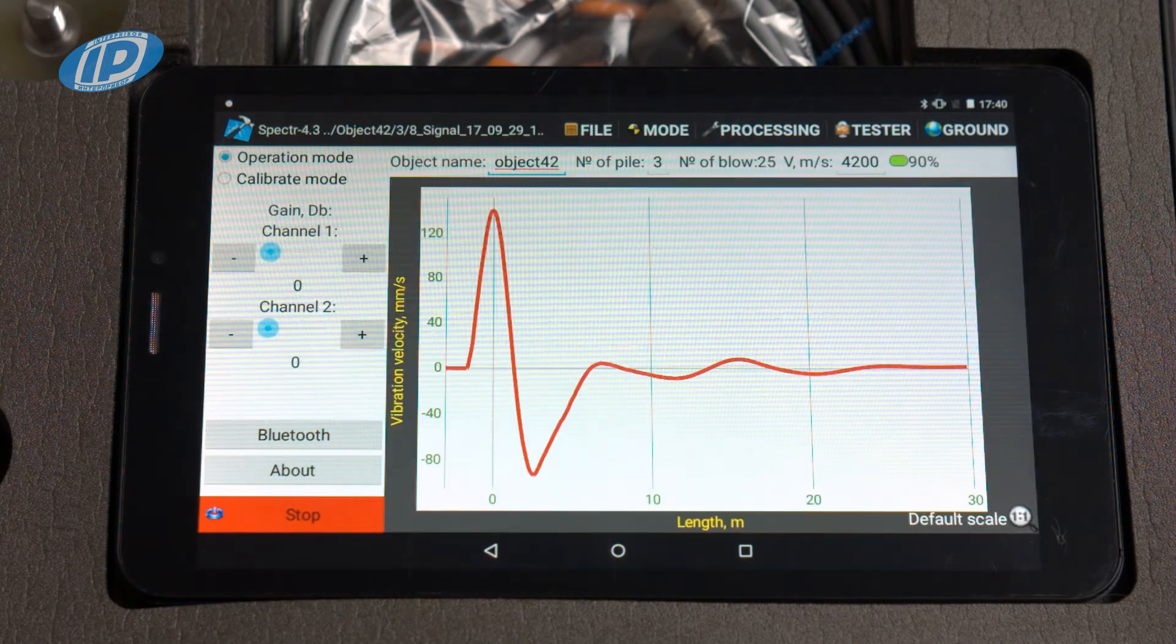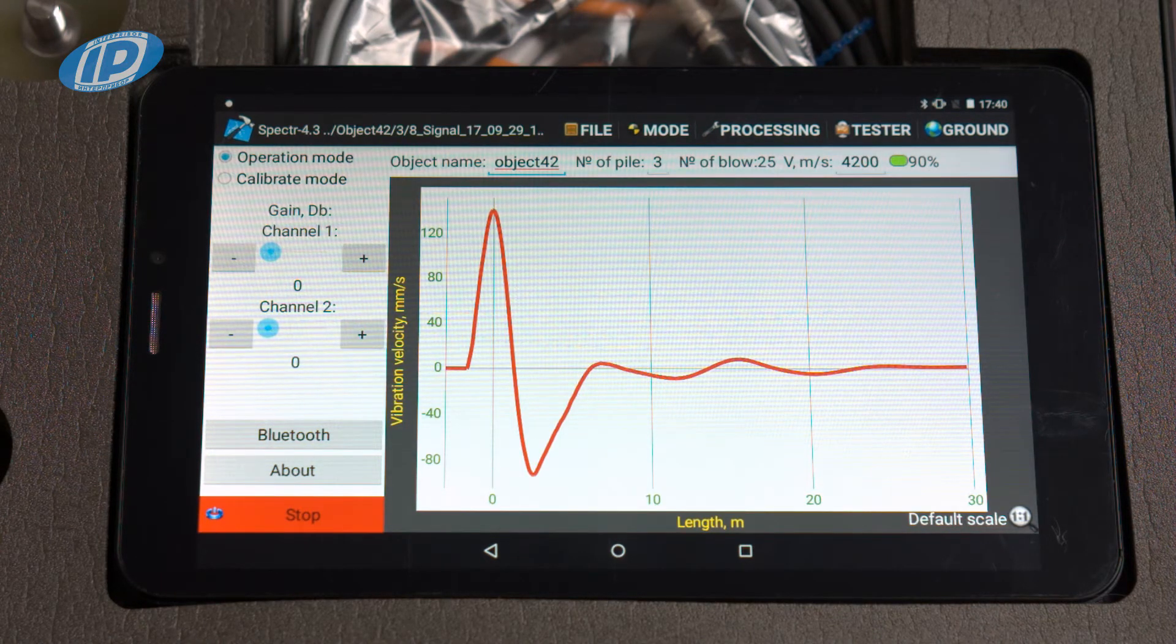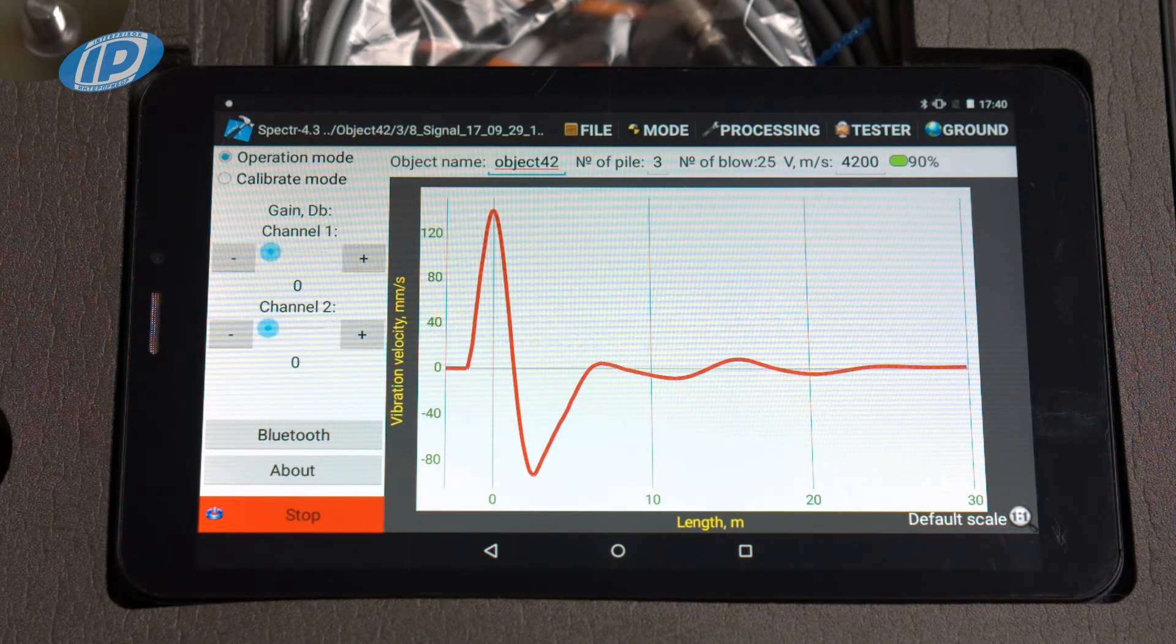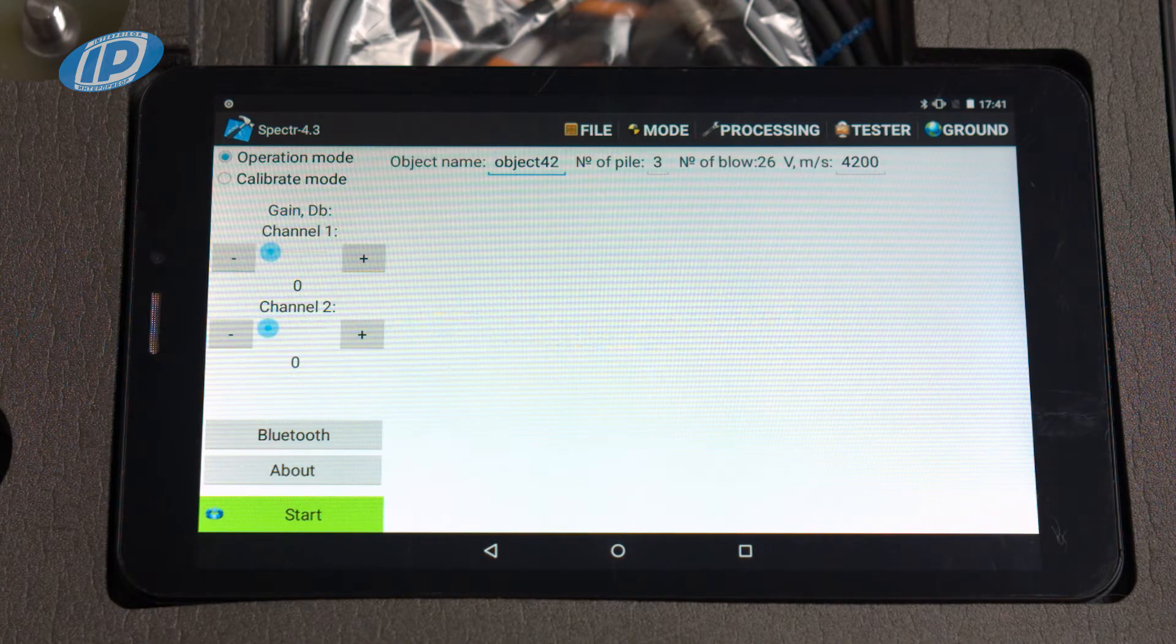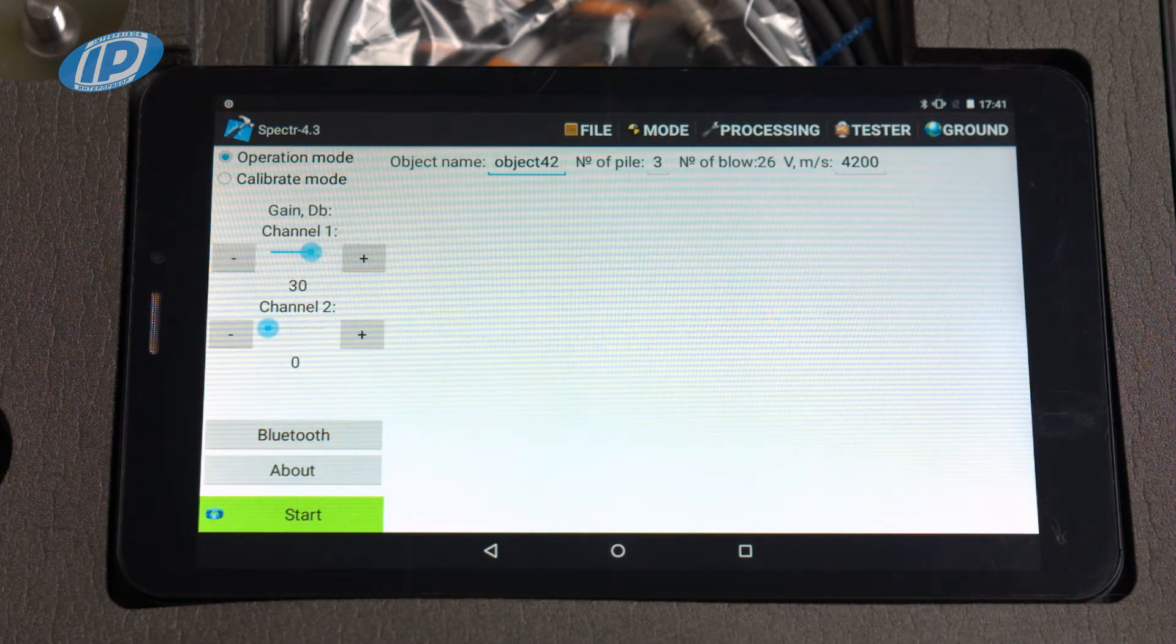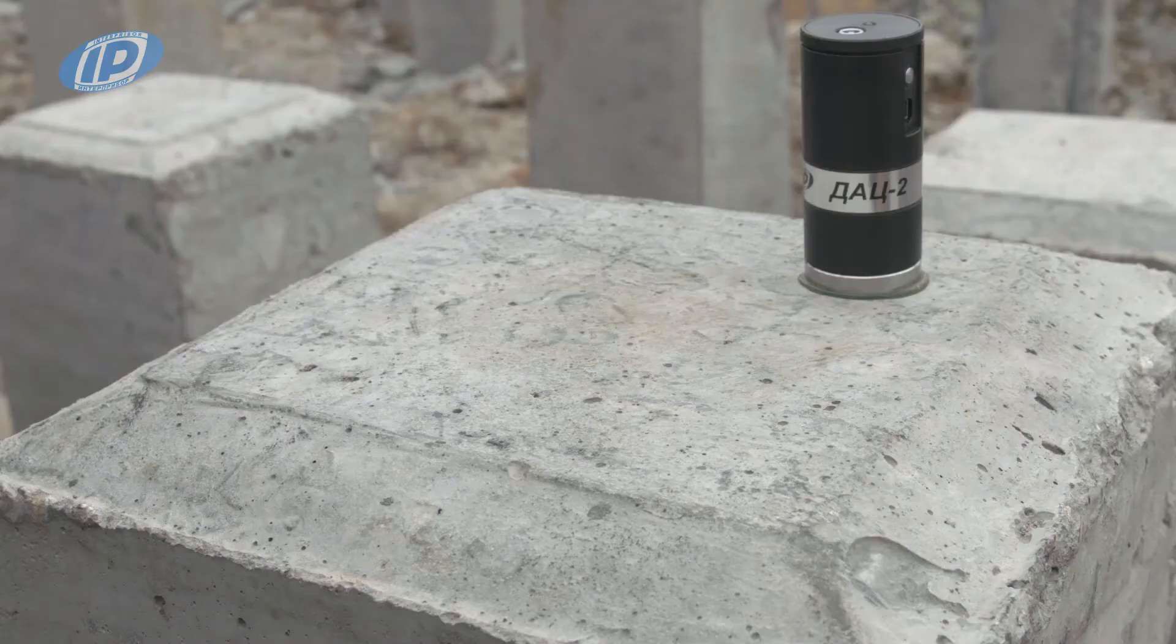The tester records the signal from the sensor, displays the signal on the screen, and automatically saves it. If the tester does not display a signal as a result of the blow, you should increase the amplification factor of the first channel and repeat the blow.